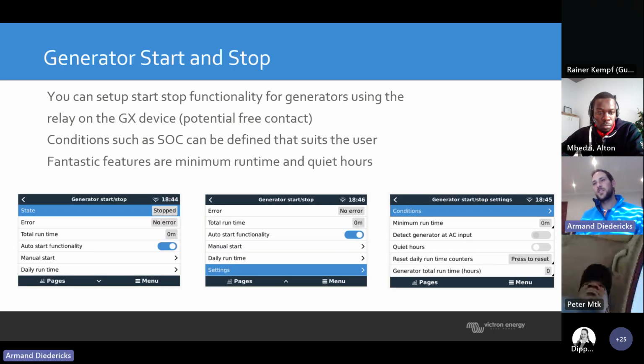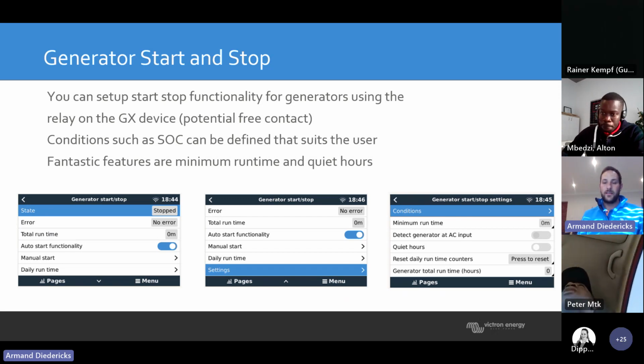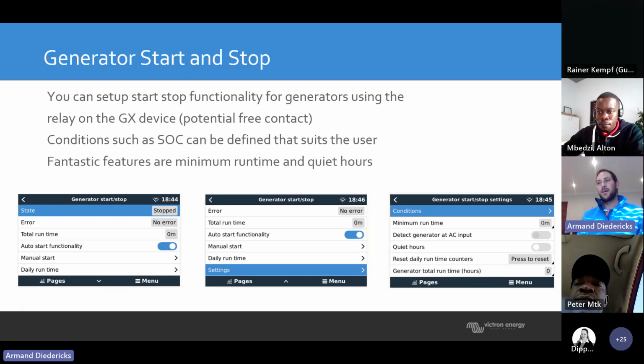All right, generator start-stop function. You can set up generator start-stop functionality for generators using the relay on the GX device, or you can use a relay in the inverter. You just need to program the system via the assistants. So conditions such as SOC can be defined to suit the user. Fantastic features are minimum runtime and quiet hours.